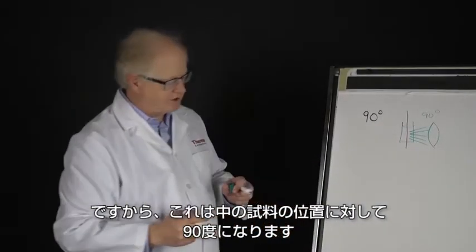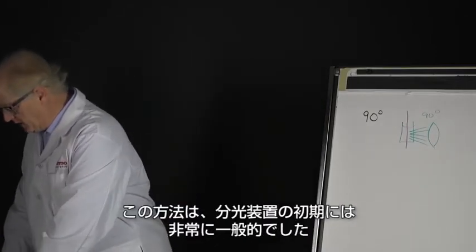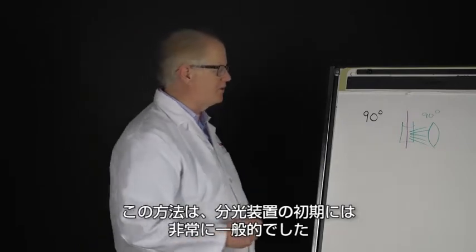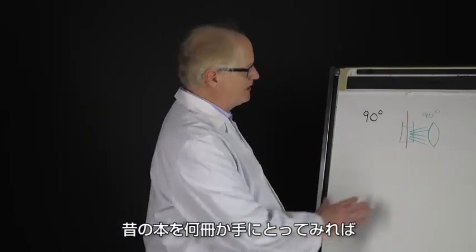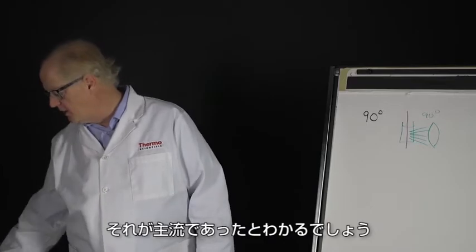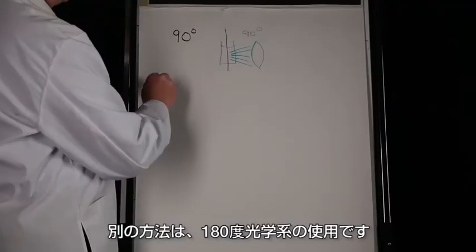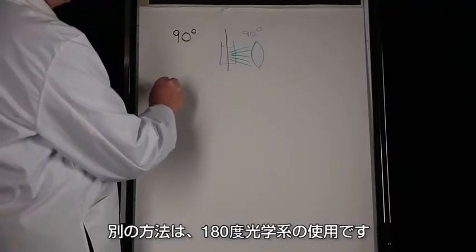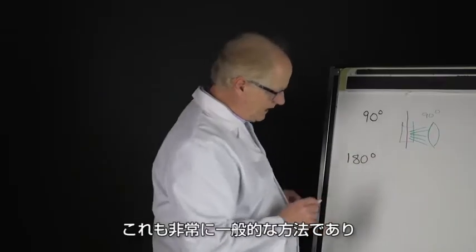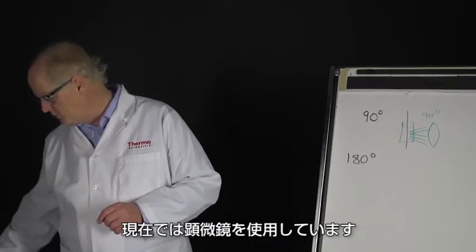That was very common in the early days with spectrometers. If you go back and look at some of the historical books, that's the way you'll see things done. But another way to do this is using 180-degree optics, and that's the other most common configuration nowadays.